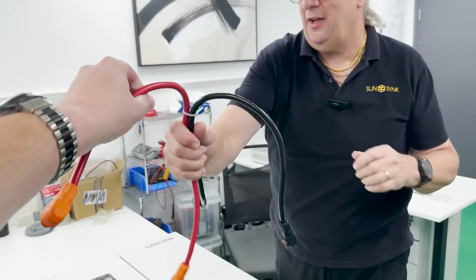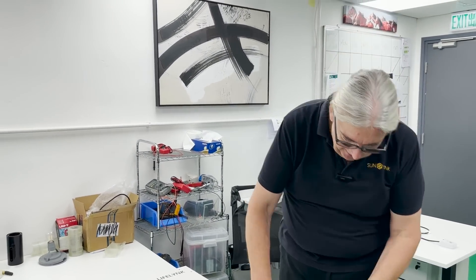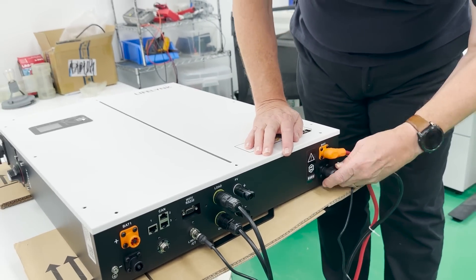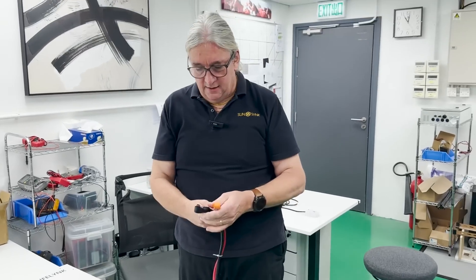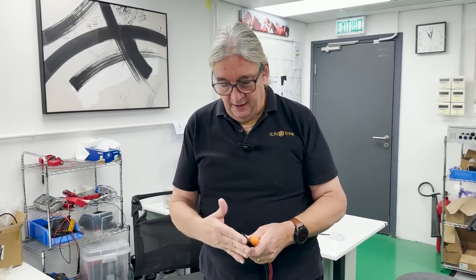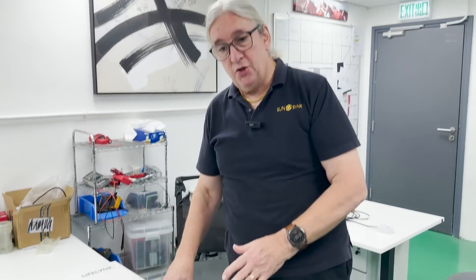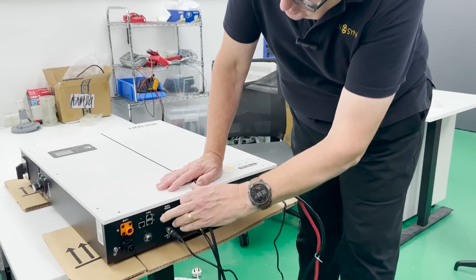The only other things to be aware of: I've got the cables here if we're going to add an external battery. The external battery can clip on either port — they're both in parallel, so it doesn't matter. These are what they call Amphenol connectors. The Amphenol connector can connect onto a standard battery, or you can use an Amphenol-to-spade adapter. If you're going to parallel two of these units together, you simply connect them and plug in.